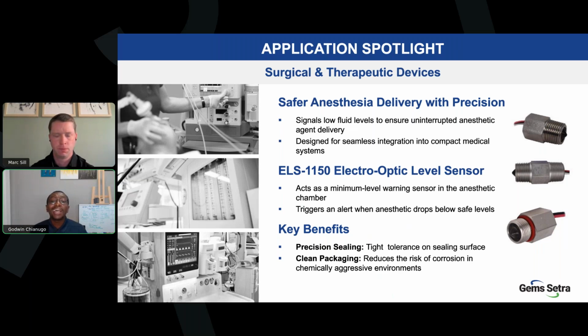The ELS 1150 has a tight tolerance on sealing surface and a fine surface finish. And this aids the customers and the manufacturers because it prevents leaks of toxic anesthetics. We know some anesthetics could be toxic and volatile, so any leakage could pose a serious risk. Our engineers designed this precise sealing interface with tight diameter tolerances and a polished surface finish, effectively preventing these leaks.